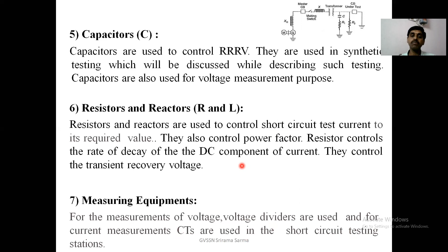Resistors control the rate of decay of the DC component of the current, because we know the rate of decay of the DC component depends upon the time constant L by R. By changing the value of the resistance, the time constant can be changed so that the transient will die out quickly. So they control the transient recovery voltage. Now measuring equipment. For voltage measurements, voltage dividers are used. For current measurements, CTs are used in short circuit testing stations. So these are the various equipment used for measurement purposes as well as short circuit testing purposes.